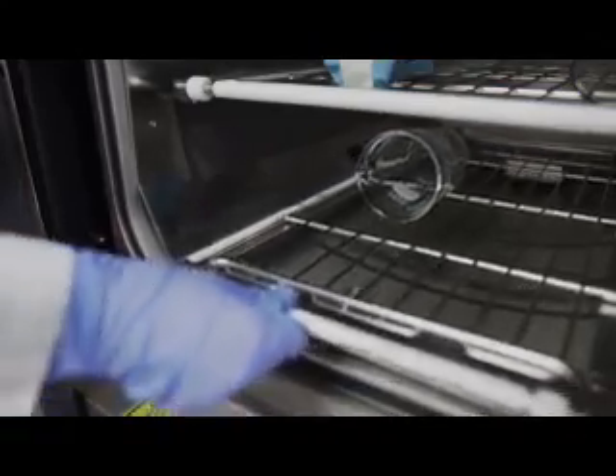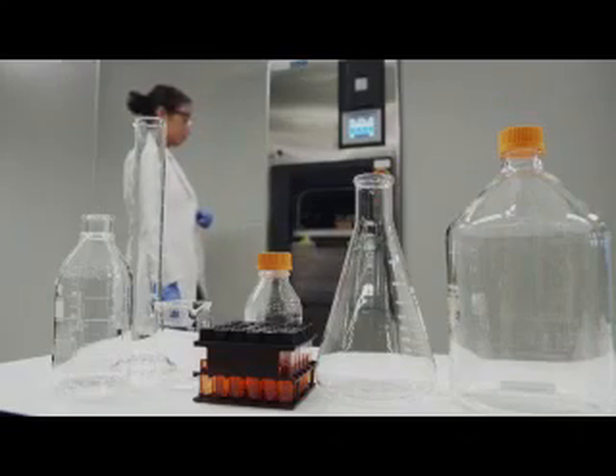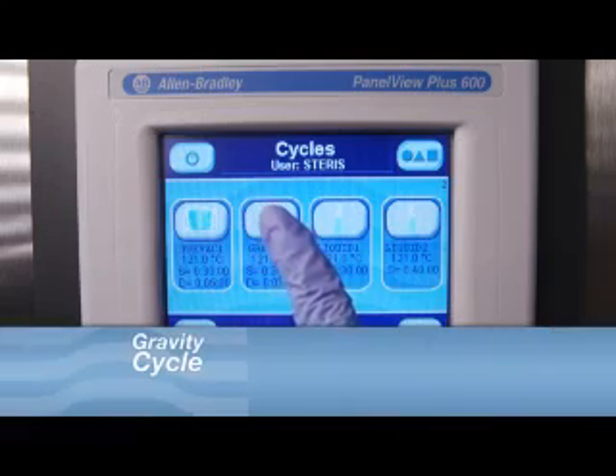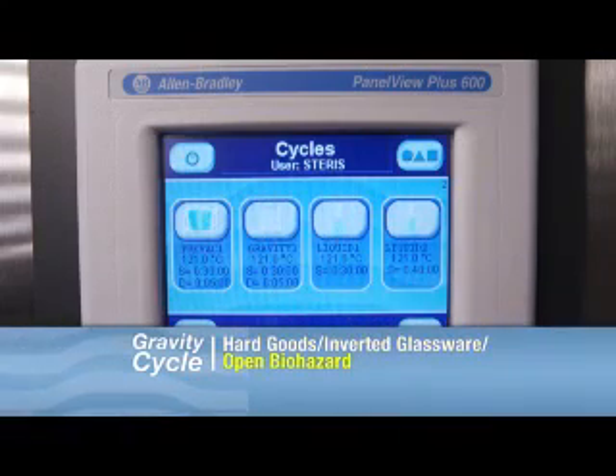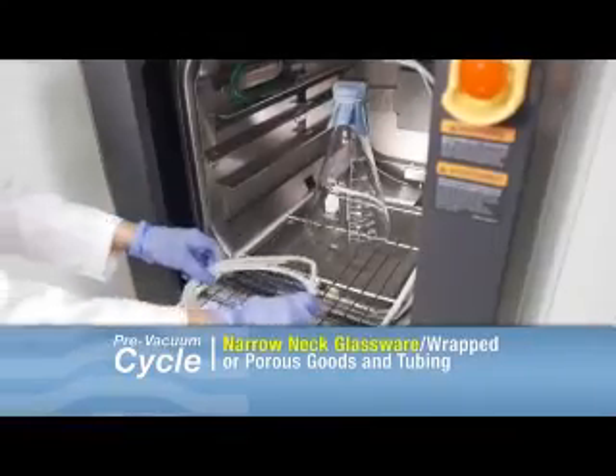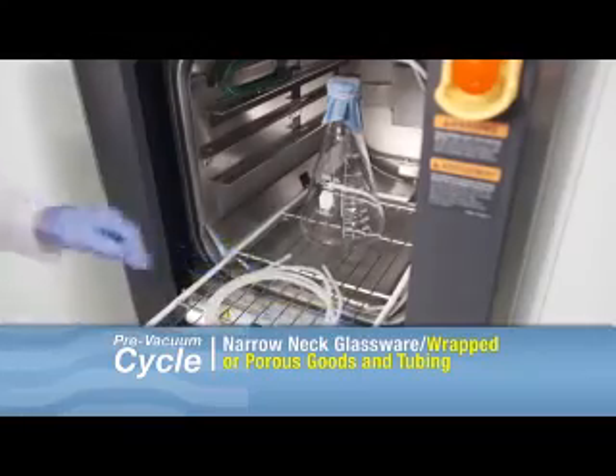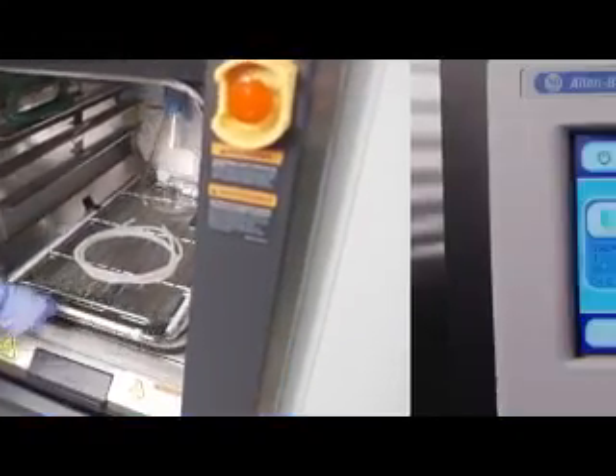Once the load is complete, the appropriate sterilization cycle can be initiated. For basic sterilization of glassware and other hard goods, the gravity cycle is a good option. For items that might trap air, such as glassware that cannot be loaded upside down, tubing, or wrapped goods, the pre-vacuum cycle is the best option.